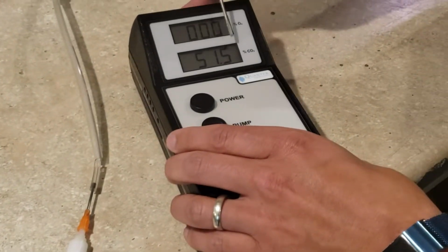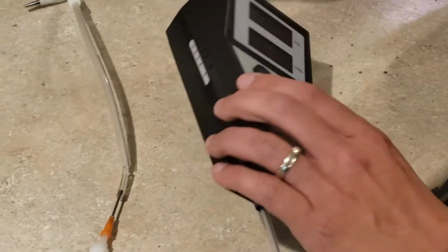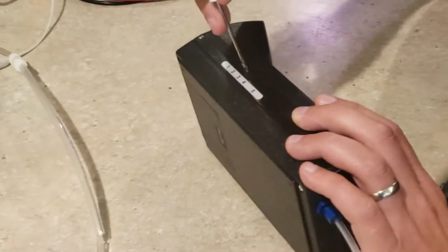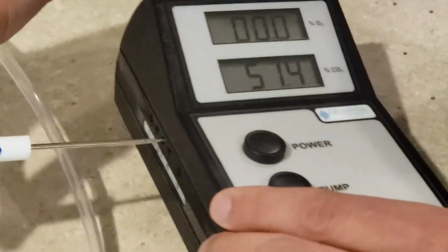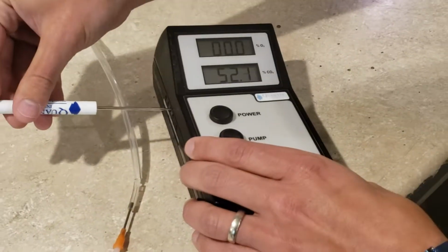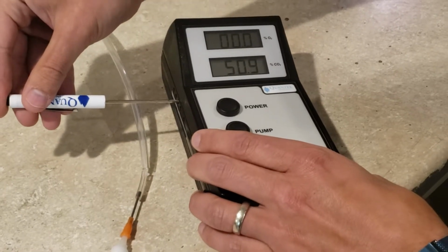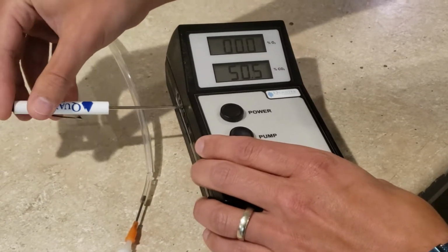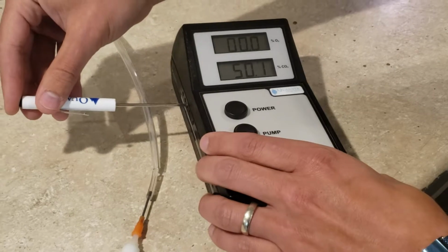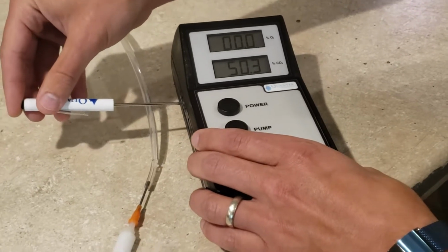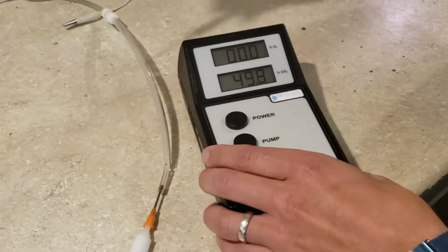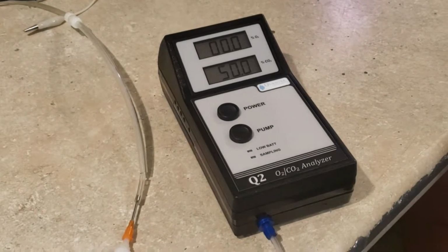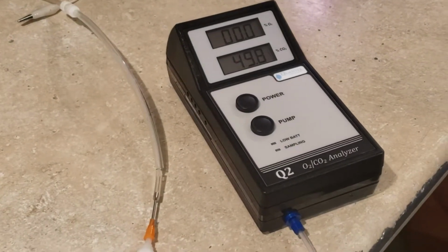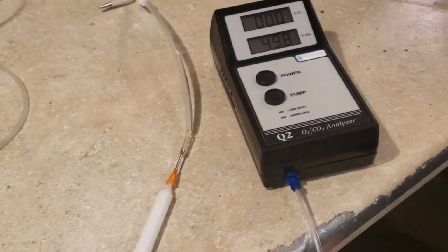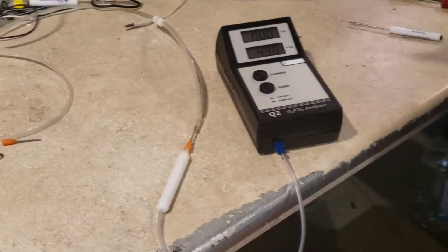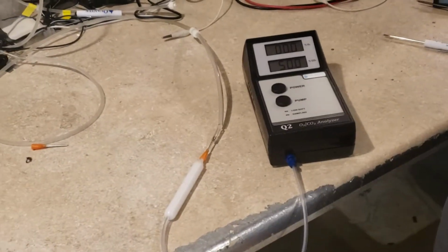And 51.5 is where the CO2 stopped. So the span pot for the CO2 is the third pot here. I'm just going to turn that ever so slightly, and I'm going to get that right down to 50%. And if it bounces around a little bit, 0.1, 0.2, that's not the end of the world. You just want to get it as close as possible. So that's good at 50.0 or 49.8. And then the last thing we want to do is check one more point. So we're going to go ahead and check 100%.